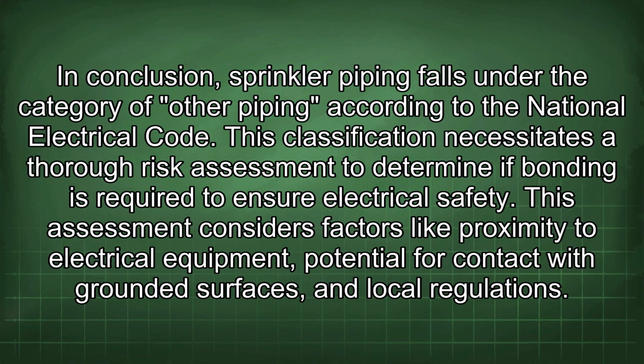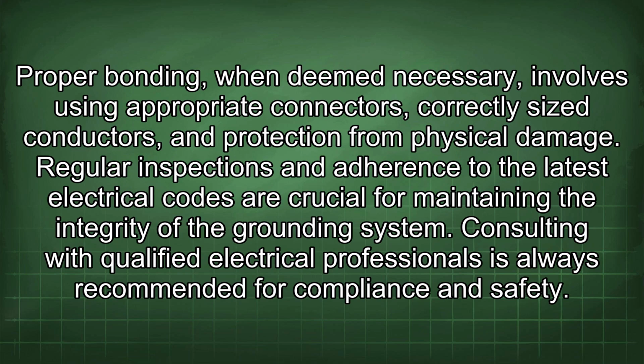for everyone. In conclusion, sprinkler piping falls under the category of other piping according to the National Electrical Code. This classification necessitates a thorough risk assessment to determine if bonding is required to ensure electrical safety. This assessment considers factors like proximity to electrical equipment, potential for contact with grounded surfaces, and local regulations. Proper bonding, when deemed necessary, involves using appropriate connectors, correctly sized conductors, and protection from physical damage. Regular inspections and adherence to the latest electrical codes are crucial for maintaining the integrity of the grounding system. Consulting with qualified electrical professionals is always recommended for compliance and safety.